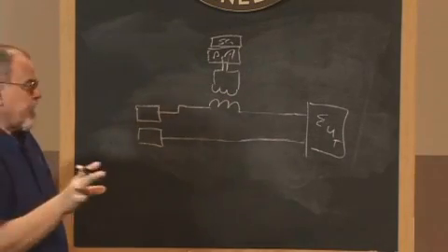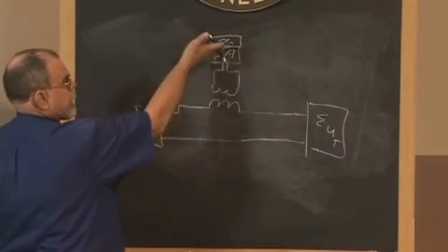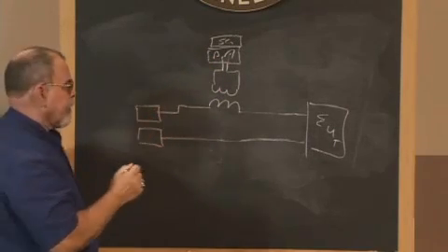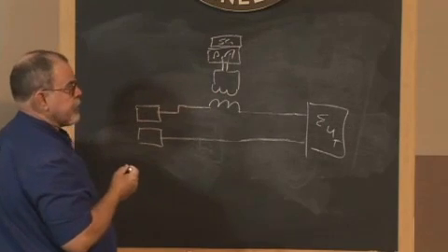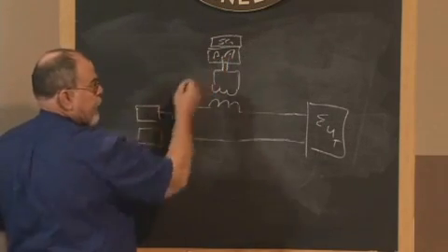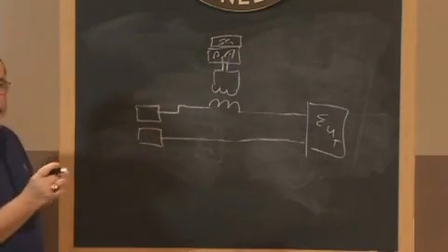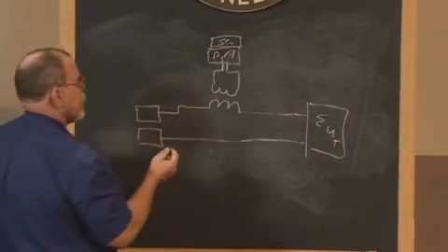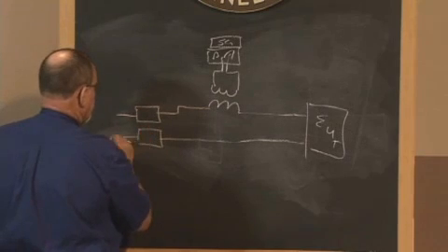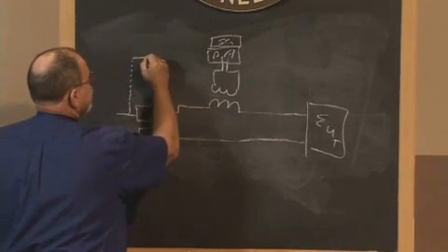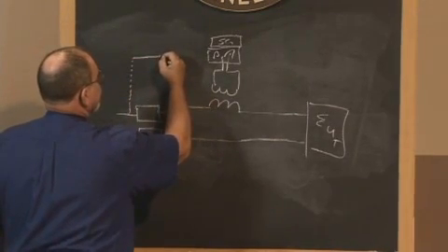I mentioned that feedback presents from 60 hertz coming back across the line into this item. For very high currents, this feedback presents too much power into the power amplifier and causes it to shut down as a protection mode. Now, we can stop this by taking our primary voltage into another transformer.